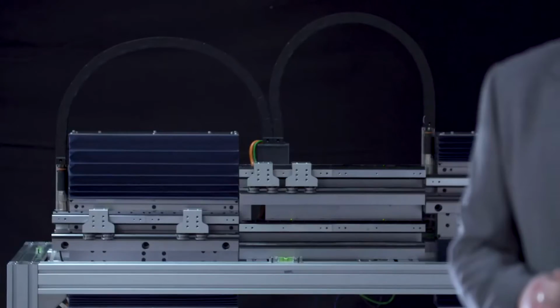It also allows for simple setups like this, where we simply have two switches. And the switches then can be positioned very close together. So here we have two rails that are very narrow, and we can move movers from one side to the other side, making a very compact XTS system, and have the added benefit that the mover never has to rotate in the other direction. If I do applications where I have two movers holding the same product, this makes it very simple. I no longer need to drive through a curve holding the product. I simply drive onto a switch, move up, and I drive off the switch.